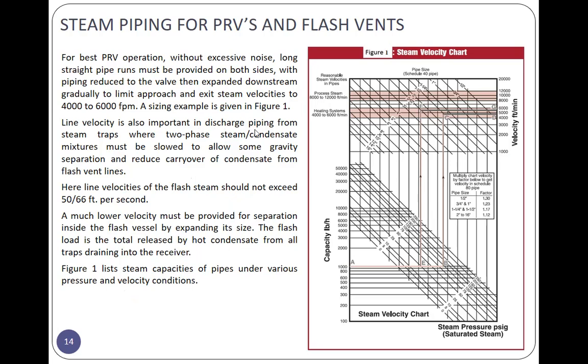Line velocity is also important in discharge piping from steam trap where two-phase steam condensate mixture must be slowed to allow some gravity separation and reduce carryover of condensate from flash vent line. Here, line velocities of flash steam should not exceed 50 to 60 feet per second. A much lower velocity must be provided for the separation inside the flash vessel by expanding its size. The flash load is the total release by hot condensate from all traps draining into the receiver. Figure 1 lists steam capacities of pipes under various pressure and velocity conditions.